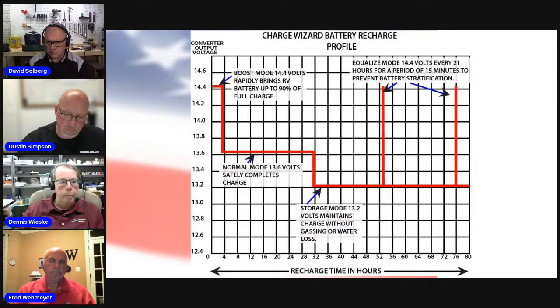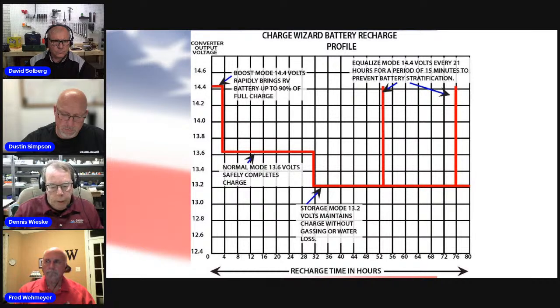If your water gets up above the bottom of the well and you're charging your battery, you may get some spitting from the taps. We don't want that either—it makes a mess, and it's going to lead to the corrosion or oxidation you see on the top of the battery posts. We don't want that. So in basic, that's the charging.